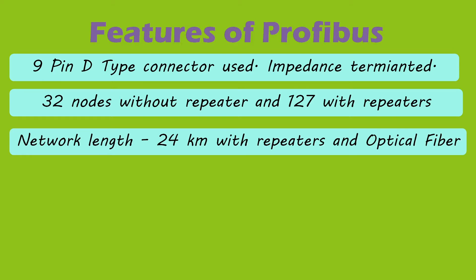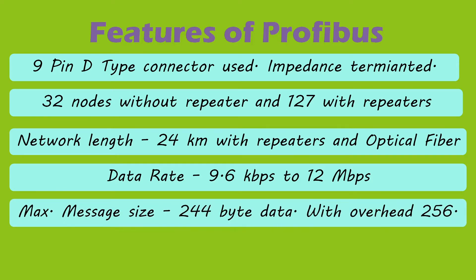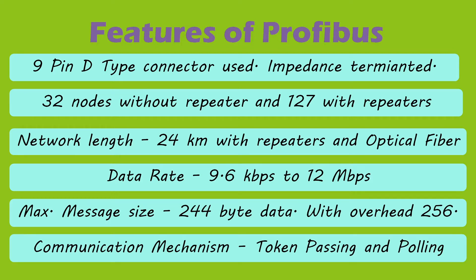The total network length supported is 24 km with repeaters and optical fiber transmission. Data speed varies from 9.6 kbps to 12 Mbps on a Profibus network. Message size can be 244 bytes of data per message per node with an additional overhead of 12 bytes, resulting in a maximum message length of 256 bytes. Messaging is done by two mechanisms: polling and token passing.